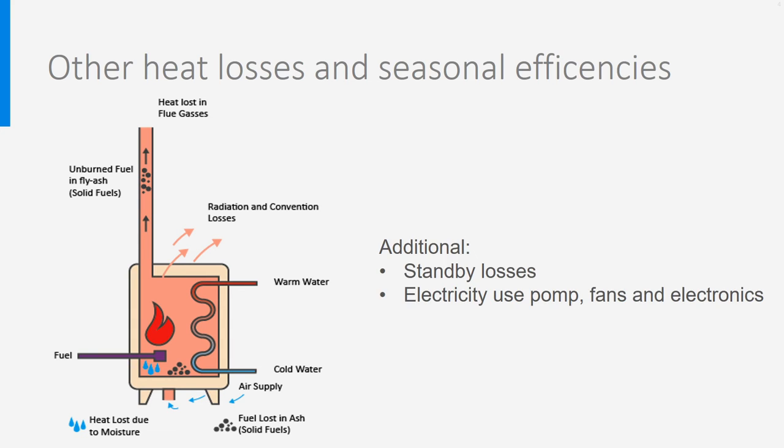We should not forget the so-called standby losses. When no heat is needed, the boiler switches to standby mode, in which the burner periodically starts heating the few litres of water in the heat exchanger and pipes. Standby losses generally amount to 1-2% of total energy use. In addition, some electricity is used for the electronics in the control system, the fans in the boiler, and the circulation pump for the radiator water. This electricity use is around 100-500 kWh yearly for domestic boilers, and is not accounted for in the efficiency.